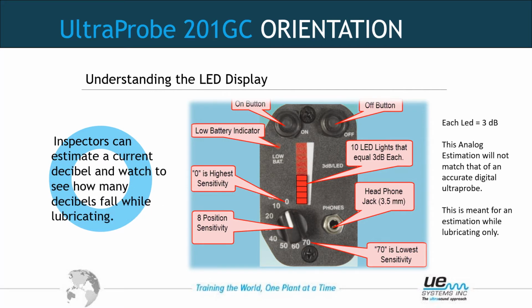In order to lubricate properly, we need to understand the 201's LED display. Inspectors can estimate a current decibel and watch to see how many decibels fall off while lubricating. Each LED equals approximately 3 decibels. There are 10 LEDs. Here we have 5 that are illuminated. Multiply 5 times 3 for each LED, and that means that's 15 decibels.